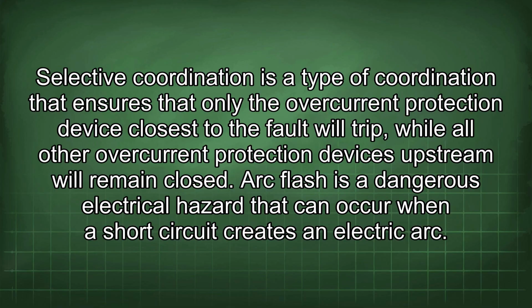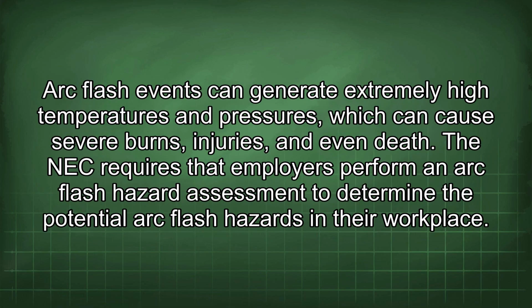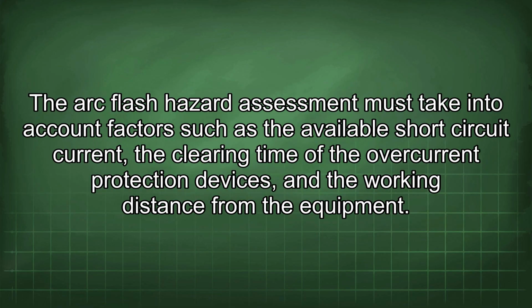Arc flash is a dangerous electrical hazard that can occur when a short circuit creates an electric arc. Arc flash events can generate extremely high temperatures and pressures, which can cause severe burns, injuries, and even death. The NEC requires that employers perform an arc flash hazard assessment to determine the potential arc flash hazards in their workplace. The arc flash hazard assessment must take into account factors such as the available short-circuit current, the clearing time of the overcurrent protection devices, and the working distance from the equipment.